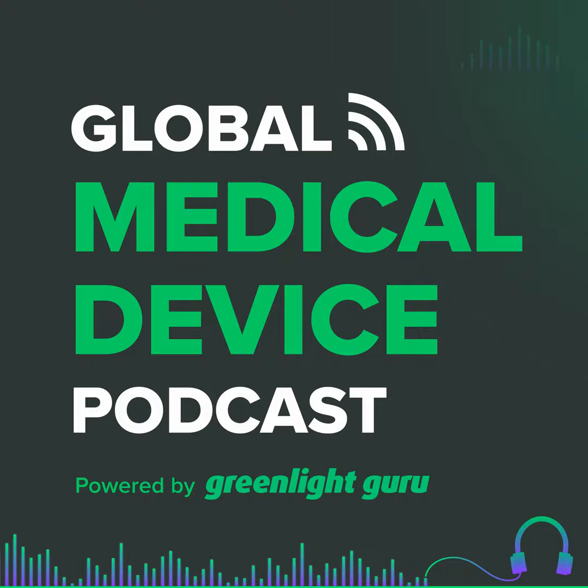The problem is there is no official document that FDA will give you that says this is an NSR device, because they'll give you an IDE if it's an SR device, but there is no non-IDE document if it's not. And so we had to go back to the IRB and say, look, there's no regulatory requirement for us to give you a document from the FDA. Oh, by the way, we took it to the FDA as a pre-sub, and we can share with you our meeting notes where everybody seemed to agree that this is NSR.